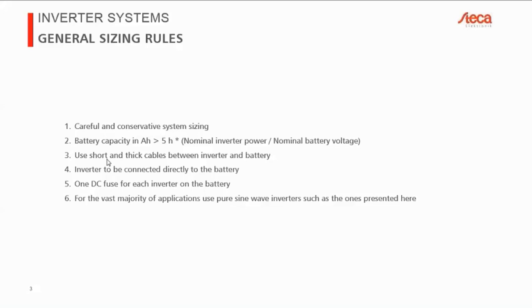With some of our inverters, the cables are already included. So for example, for the SOLARIX PI inverters, we already have 16 millimeter square cables that are prefabricated, so that are already attached to the inverter, so you don't need to worry too much about that. But for the bigger inverters where you design your own system, where you have to basically attach your own cables, make sure that you follow the instructions in terms of the cable cross-section. Otherwise, you'll run into issues.